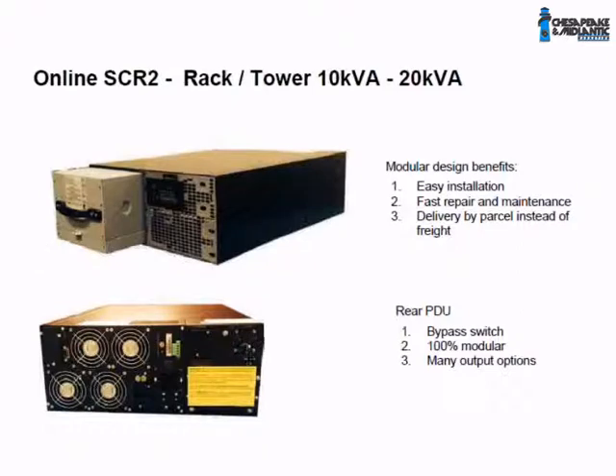It comes standard with a maintenance bypass switch right on the back, and this is actually a detachable module. So if the whole electronics in the UPS failed, there's like 4 bolts here - you undo those bolts, and the only thing left in the rack is going to be this module right here. You slide the new one in, bolt it up, and you're good to go. So it's very easy to maintain, and it's 100% modular.